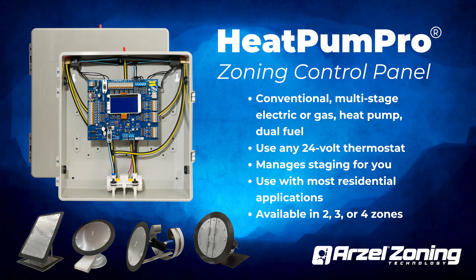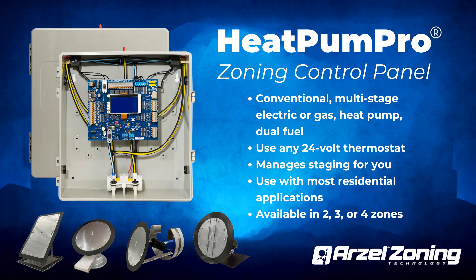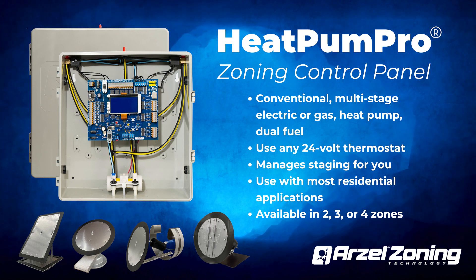If you're working with dual fuel, just program the temperature and HeatPumPro will change over to an alternate heat source at that temp. There's also a hard lockout, which you can use with electric backup heat. HeatPumPro is the zoning system you should choose for most residential applications.